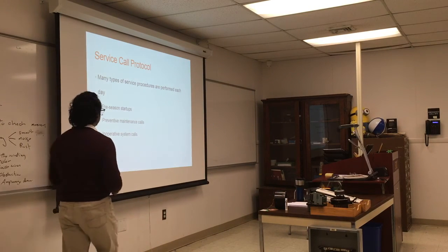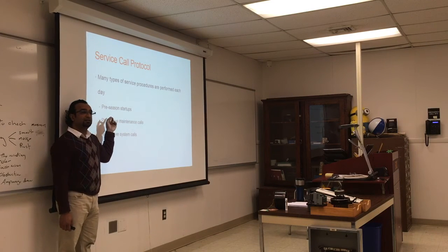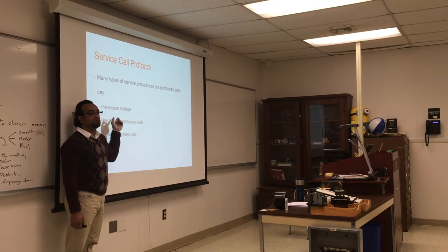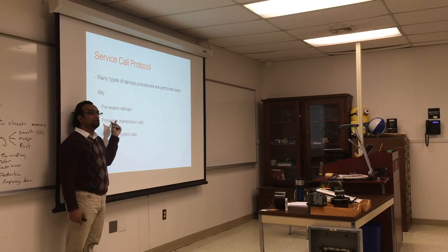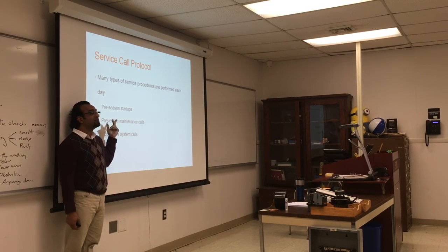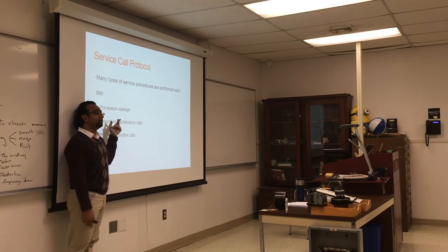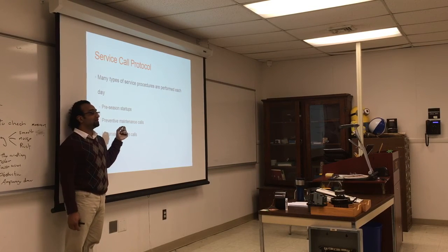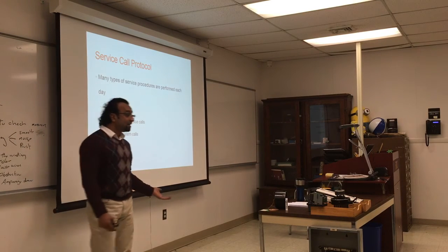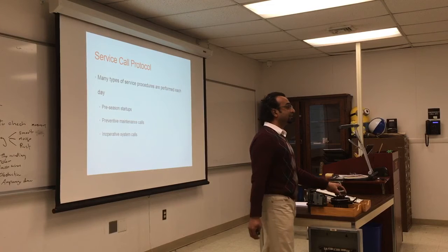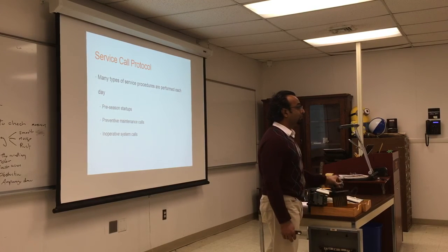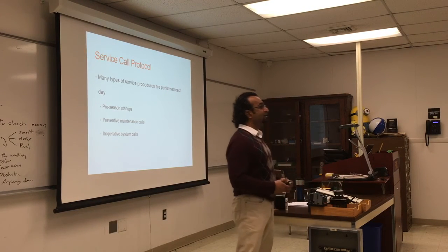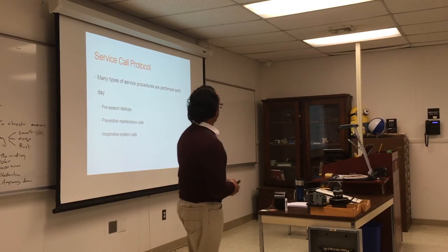So pre-season startup is always going to be a problem with the capacitor. The motor has been sitting for a while. It's rusted. It was not maintained. So you turn it on, nothing will happen. It's stuck. Sometimes the answer is as simple as giving it a push or knocking on it with a mallet. Knock out the rust and it will run. That can be a simple solution. Sometimes the motor is completely seized or oxidized and you have more obstruction from the inside. Sometimes it will help to take the motor apart, clean up the rotor and put it back again. That could help sometimes. And sometimes you have to change the motor.